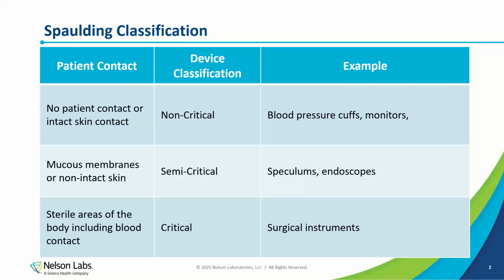as well as just simulating the use of the devices. Again, they're very complex devices that are going to come in contact with blood, but also tissue. And so during the validation testing, you're going to want to choose an appropriate test soil, but also you're going to want to consider using tissue, as these devices are going to come in contact with tissue, and in some cases they're going to have cauterizing action, so you're going to want to take into account that process as well. And they're going to have cutting action and grasping action, so you're going to want to simulate that on tissue.